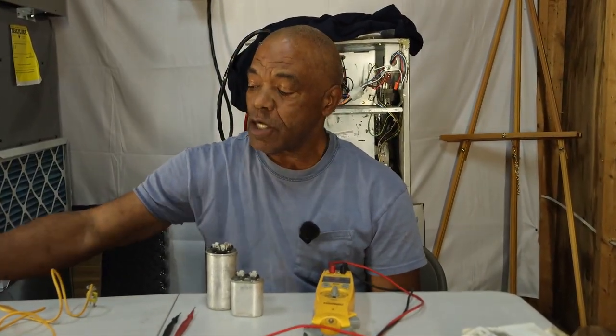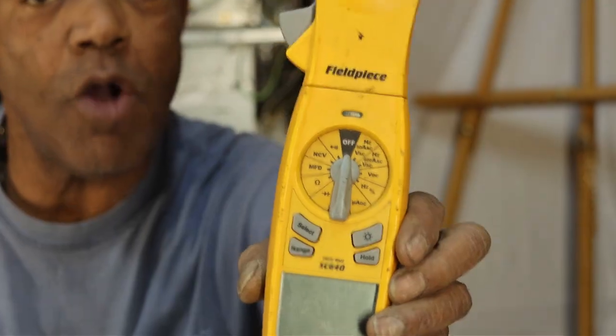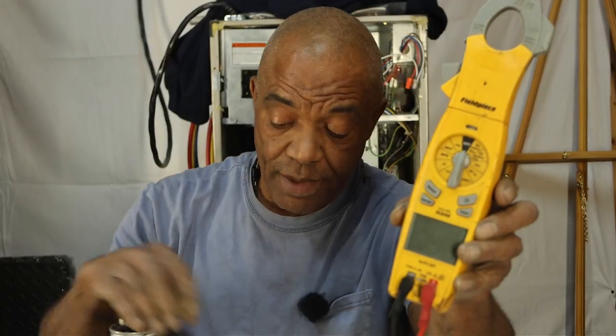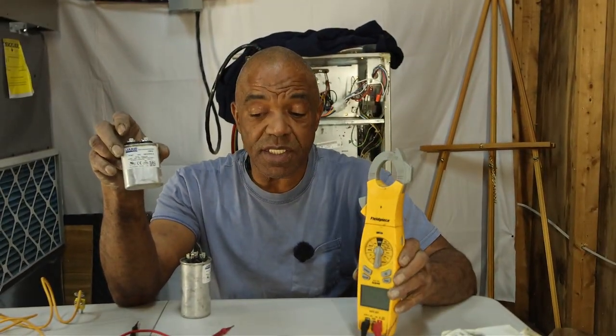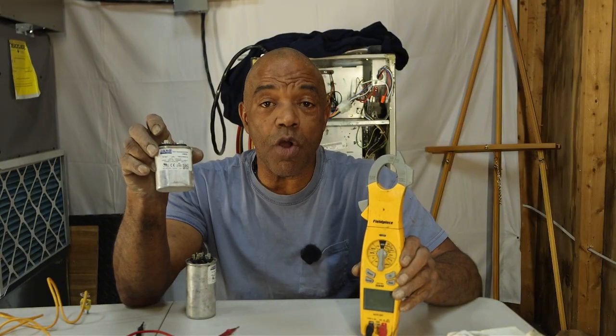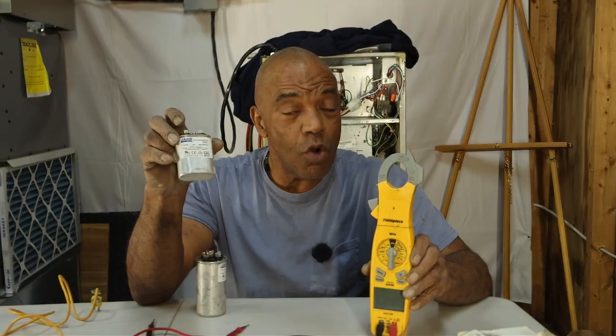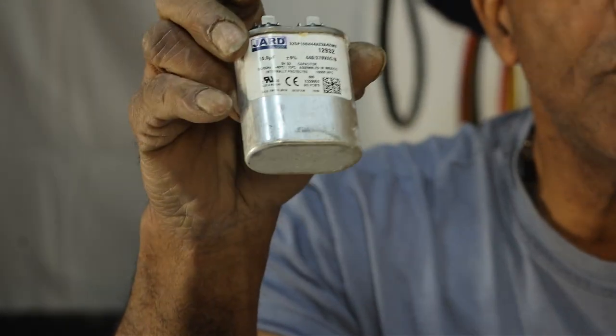Okay, let's look at the use of our amp probe. Okay, there's, like I say, our amp probe is a multimeter. Okay, one of the things we use it for is to check capacitors. Okay, capacitors, this is a capacitor for an indoor furnace or an indoor air handler. Old school. Today, most of our blower motors on our heat pumps as well as our furnaces are ECM motors, and they have the capacitor built within them.